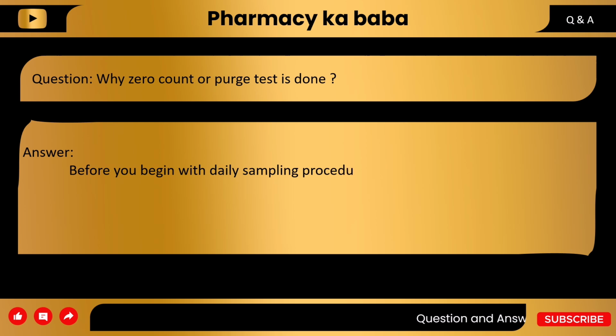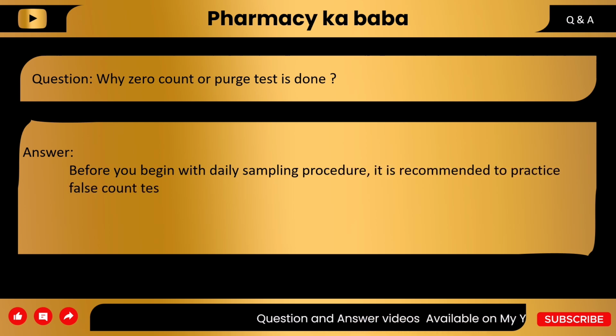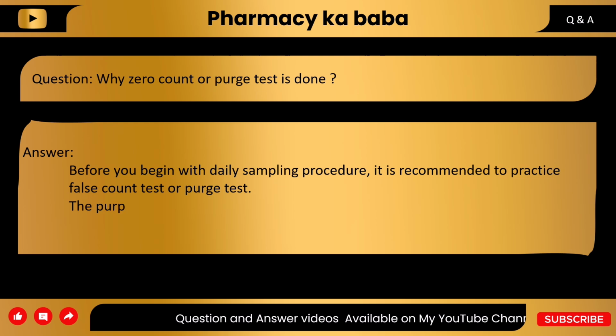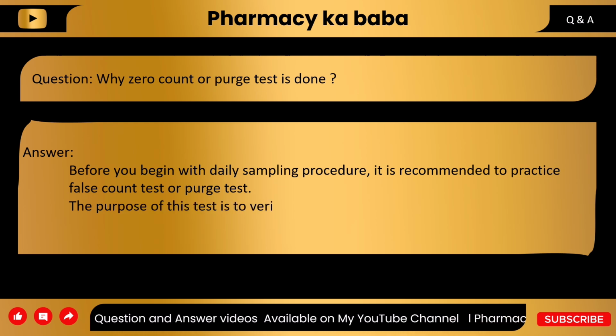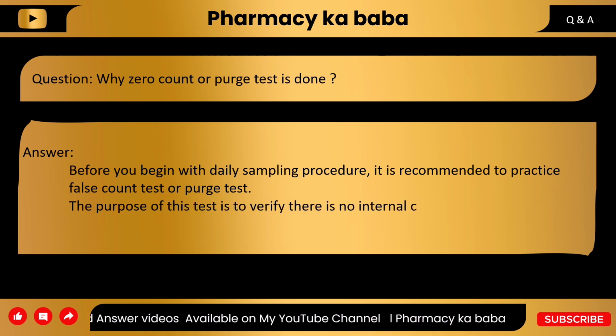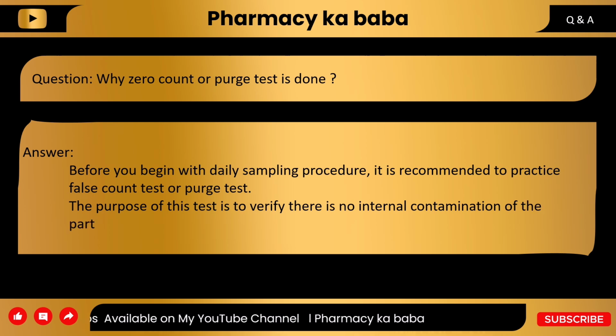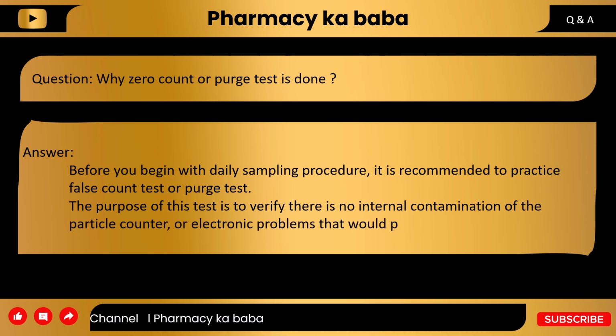Question: Why is a zero count or false count test done? Answer: Before you begin the daily sampling procedure, it is recommended to perform a false count test. The purpose of this test is to verify there is no internal contamination of the particle counter or electronic problem that would produce a false high count.